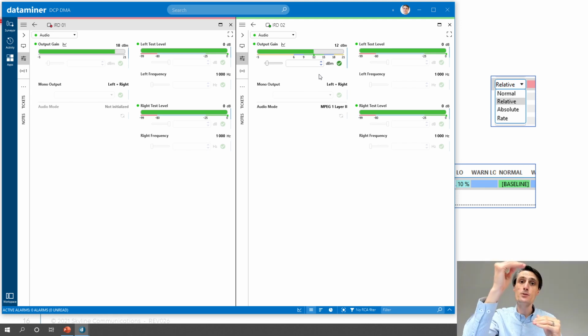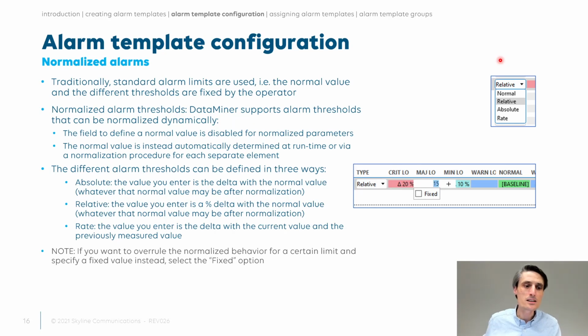But suddenly a big jump, we will generate an alarm, and if it then remains stable again or more or less stable, then the alarm will disappear. But you can pick it up with correlation, of course, to make it a persistent alarm. So that's the special case of the rate alarm. Basically, the baseline is following you in time and is using the previously polled value.